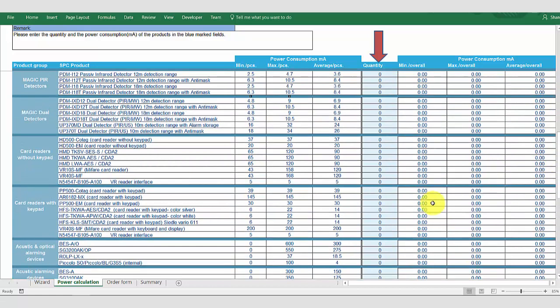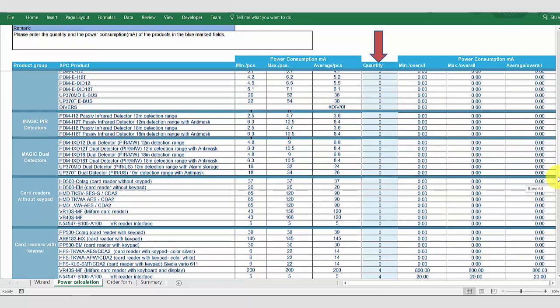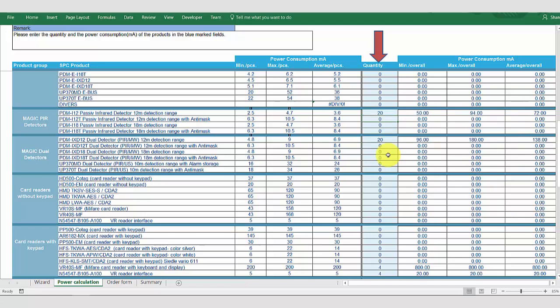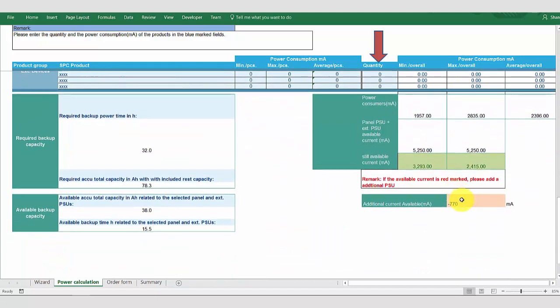We will now add additional units to the system. I'm going to add the VR40 readers for our doors, and I will add a bell to the system. We will also add a number of detectors for our zones, so we're going to add 20 PIRs. And again, we can check our power calculation and we can see we have now exceeded the additional current available.